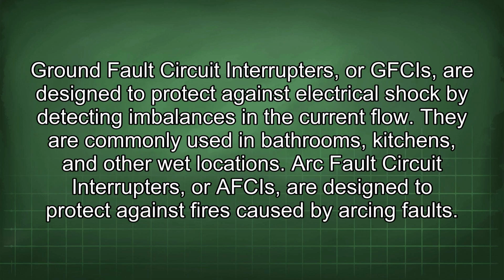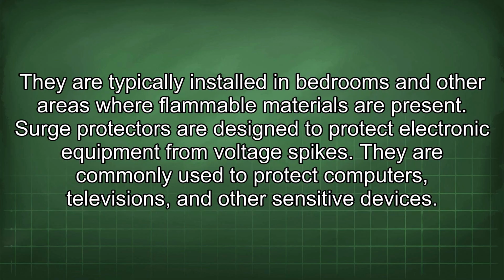Ground fault circuit interrupters, or GFCIs, are designed to protect against electrical shock by detecting imbalances in the current flow. They are commonly used in bathrooms, kitchens, and other wet locations. Arc fault circuit interrupters, or AFCIs, are designed to protect against fires caused by arcing faults. They are typically installed in bedrooms and other areas where flammable materials are present.